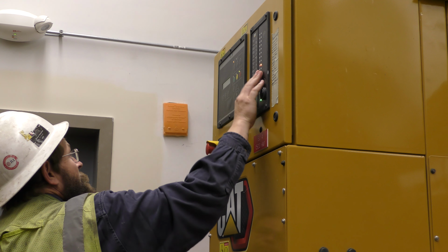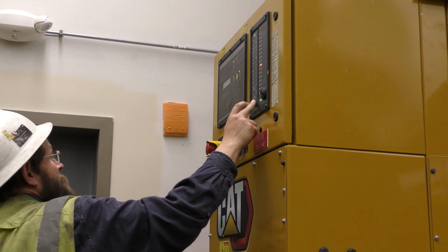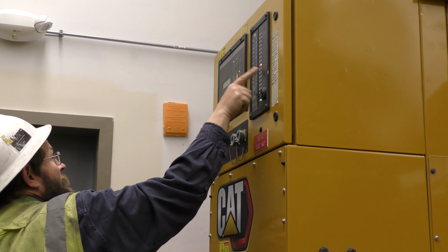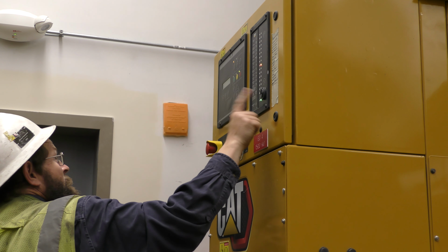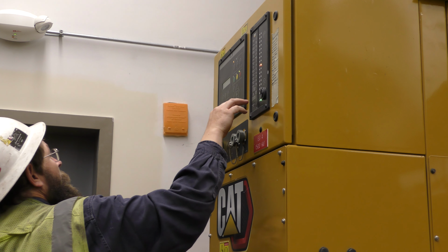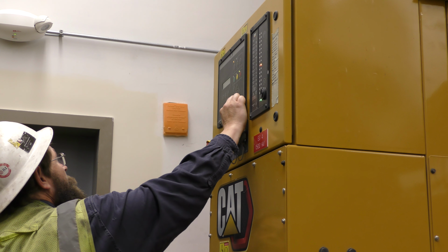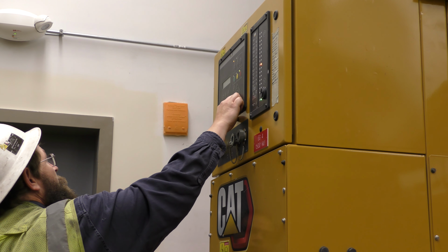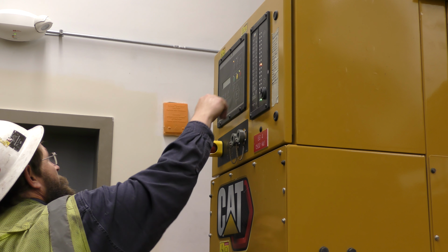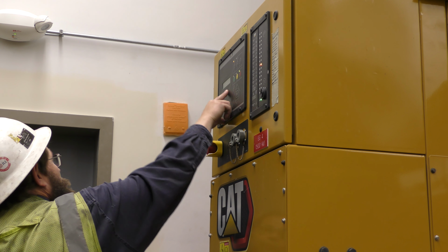Your annunciator will annunciate these set parameters, so if you come in here, yellow light's on, we're not in auto right now. This will be screaming at you. It'll tell you what alarm you have. In your event log, it'll give you other alarms too. So right now you have a genset alarm that's not in auto. You can go to that and it'll tell you which one is not in auto.